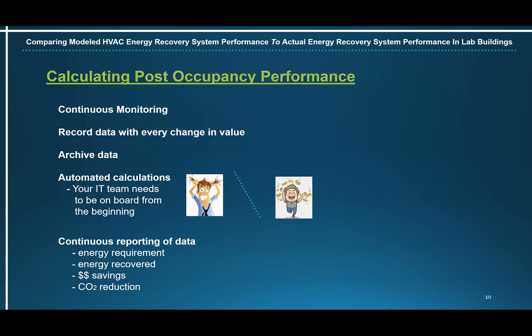Calculating post-occupancy performance. You need to monitor the system continuously so you have all the data you need. Record data with every change in value, not just hourly or once daily. You need archived data in case something looks off in performance calculations. Your IT team needs to be on board from the beginning to automate calculations — hand calculations or sorting spreadsheets will be a nightmare. For continuous reporting, you need a dashboard to display energy requirement, energy recovered, savings in dollars, and CO2 reduction, updated continuously.